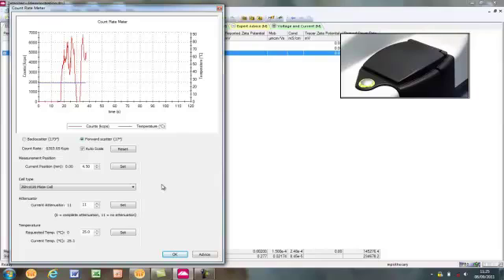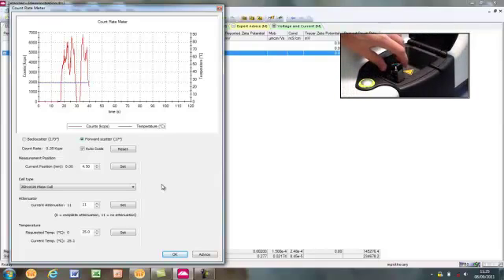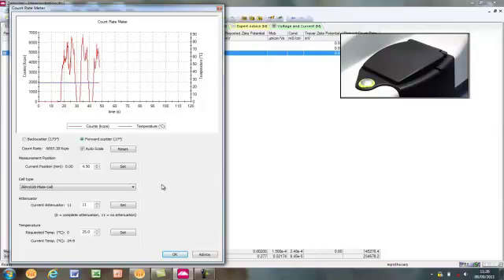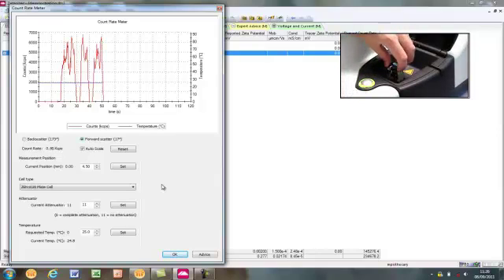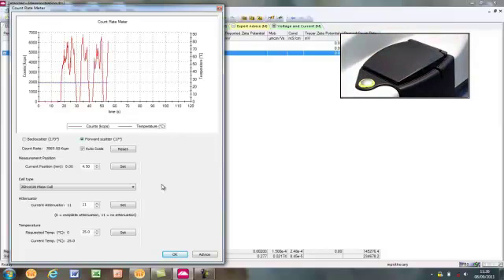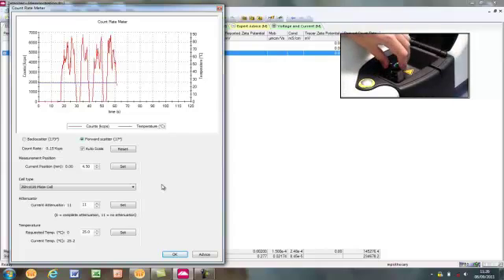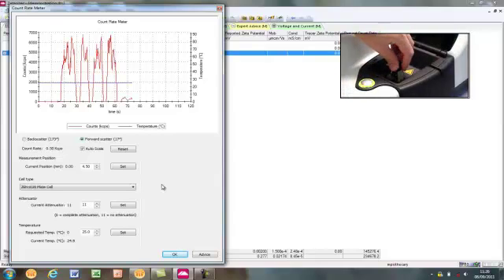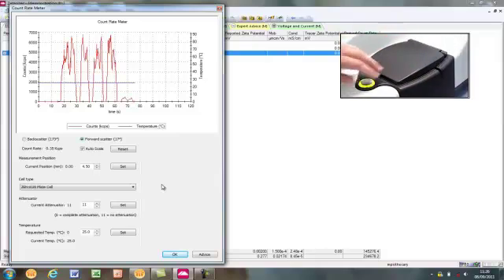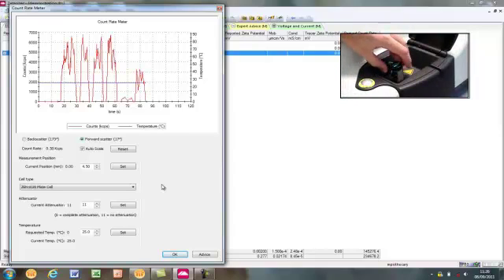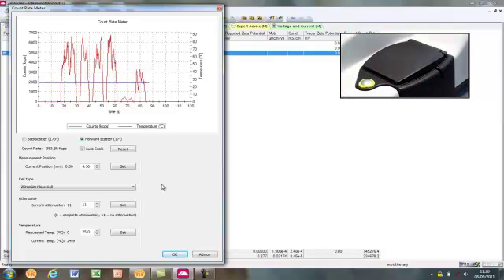Repeat this until when the lid is closed, the count rate does not return. Here, this happens after five turns of the cell cap. After the second, third and fourth turns of the cell cap, the count rate always returns to a similar level as it was at the beginning of this step. This can be seen clearly in the count rate meter. After the fifth turn, however, the count rate stays very low. Turning the cell cap back 45 degrees reveals the laser beam again and the count rate returns to its starting levels. Moving the cell cap clockwise 45 degrees again masks the laser and the count rate is lost.